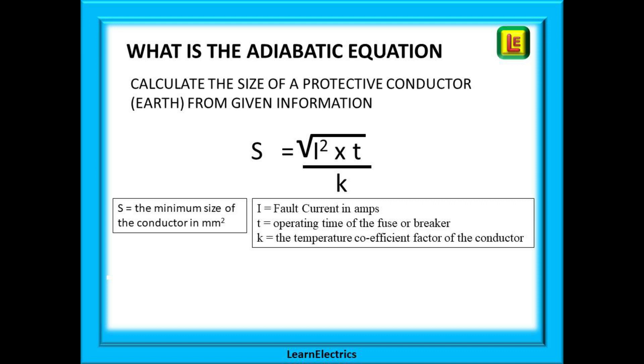What then is the adiabatic equation? It is used to calculate the size of a protective conductor or earth as it is often called. We need to know certain parameters to do with the electrical circuit and this information will be given to you in the exam question. It is all about choosing a conductor size that will carry a big fault current without overheating before the fuse blows or the circuit breaker trips.